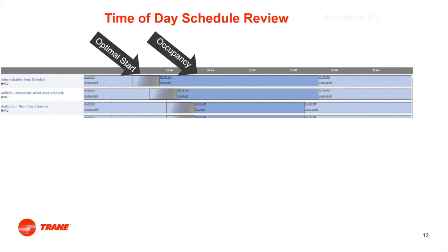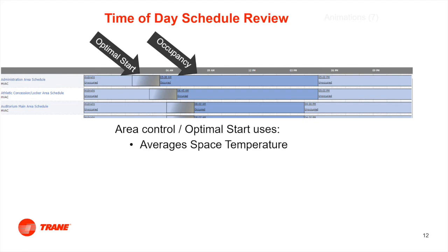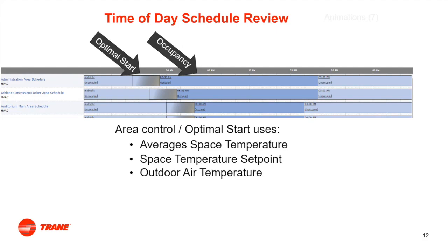This is an optimal start window. What does this mean? Well, I'm saying that I want my building to be satisfied by 5:30 a.m. But I'm also going to say you get a 2-hour optimal start window to start whenever you want to based on outside air temperature. So the days of trying to predict what the weather patterns might be, those days are over. We just say, okay, area control, you're going to look at the outside air temperature, the average space temperature, the space temperature set point of that space, and it's going to calculate all that stuff and say, okay, based on the history of how this space is working, the last time it was 50 degrees outside, it took me 30 minutes to get satisfied by 5:30.